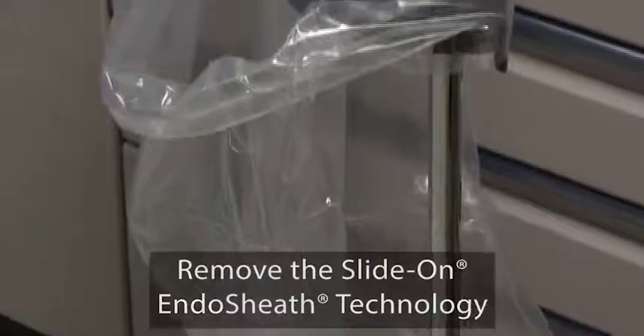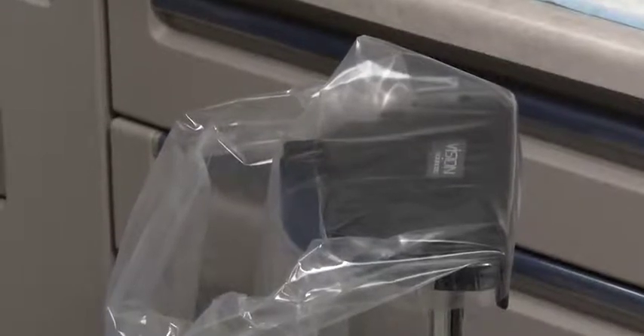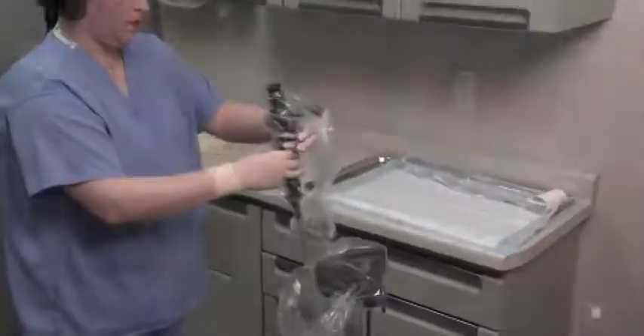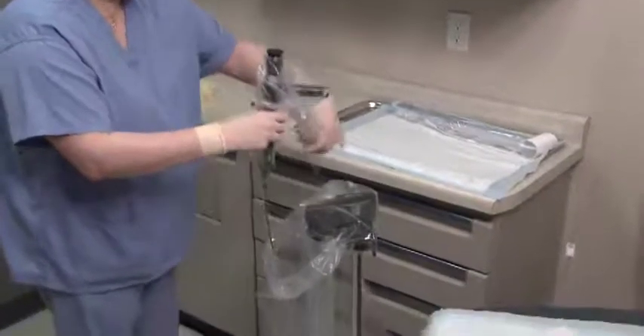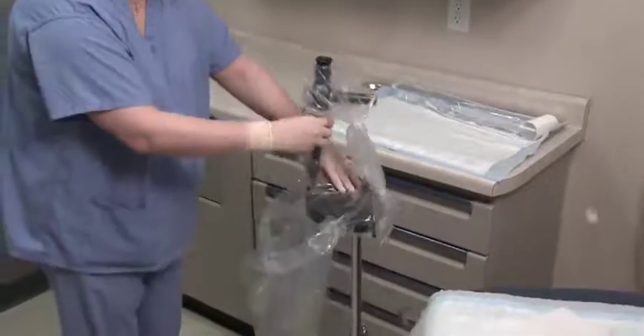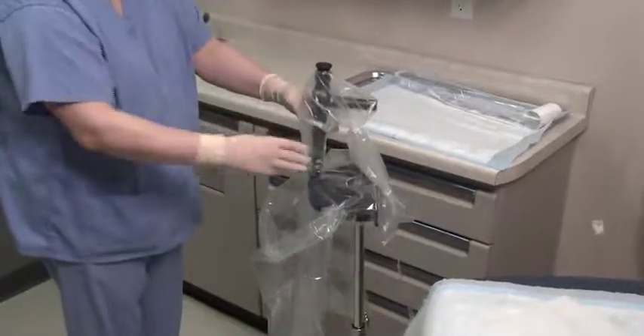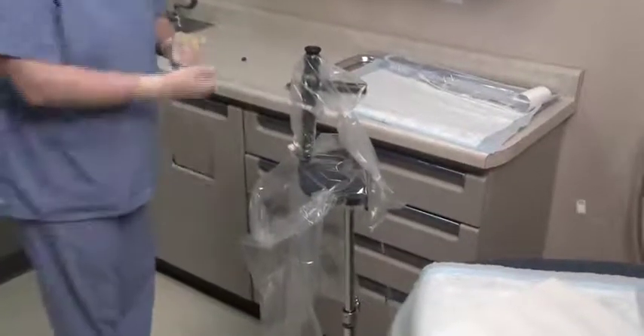Always use the installation stand to remove the endoscope from the sheath. Attempting to remove the endoscope without using the installation stand could cause damage to the endoscope. Ensure that the drape bag completely covers the installation stand. Slide the endoscope and sheath into the installation stand with the accessory port facing toward you.